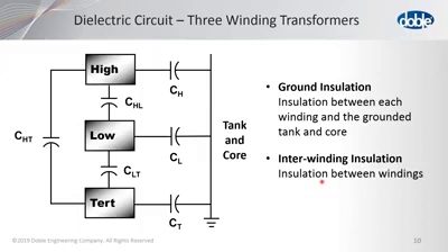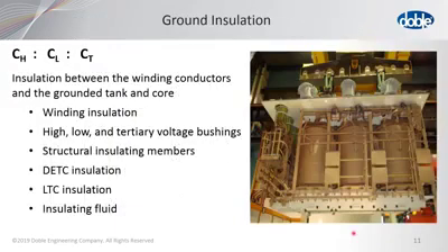Now also we have three other insulation systems that are between the windings. I'll point this out here. Between high and low is the CHL. Between the low and tertiary is CLT. And between the high and tertiary is CHT. So those are the six insulation systems that we will be testing during the testing of a three-winding transformer.